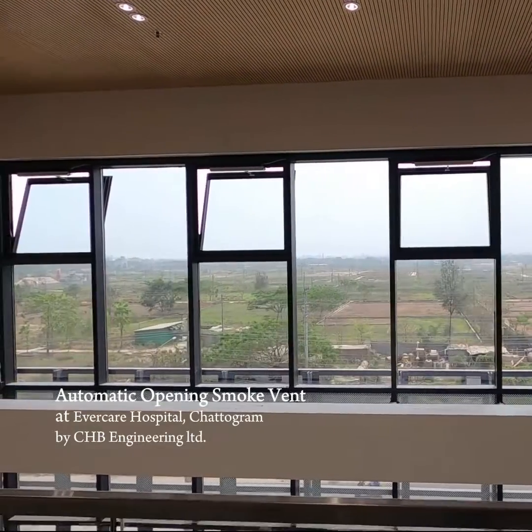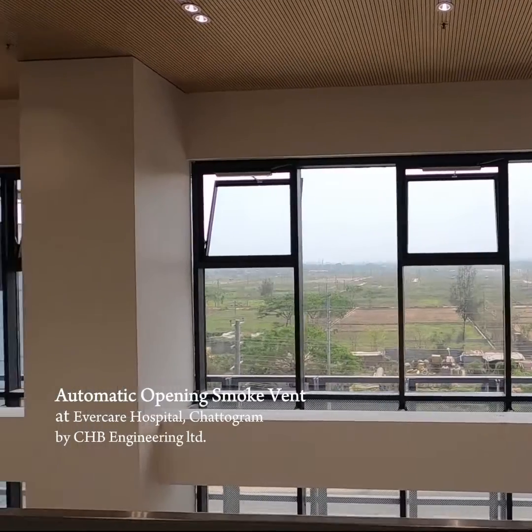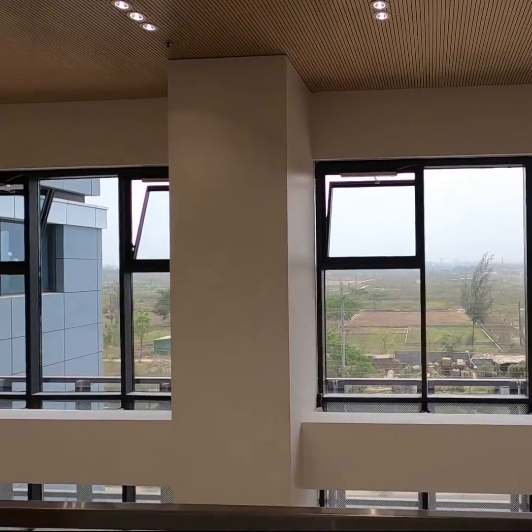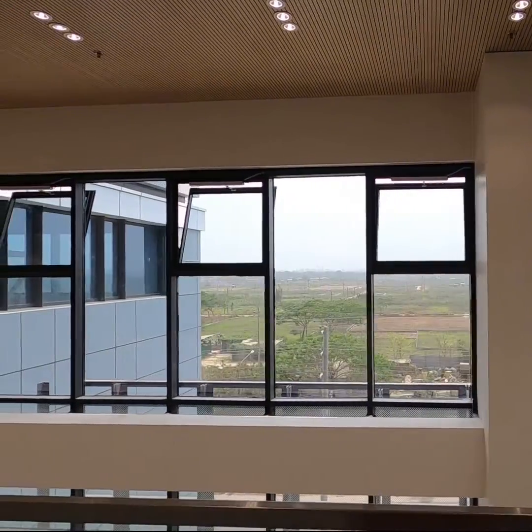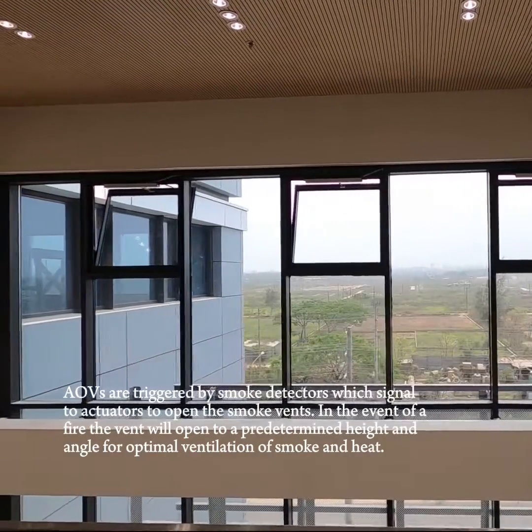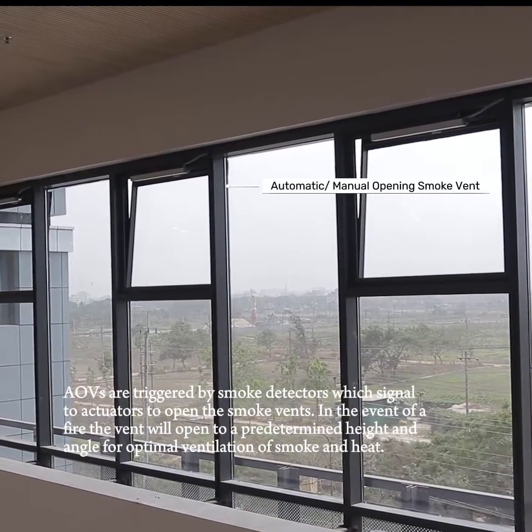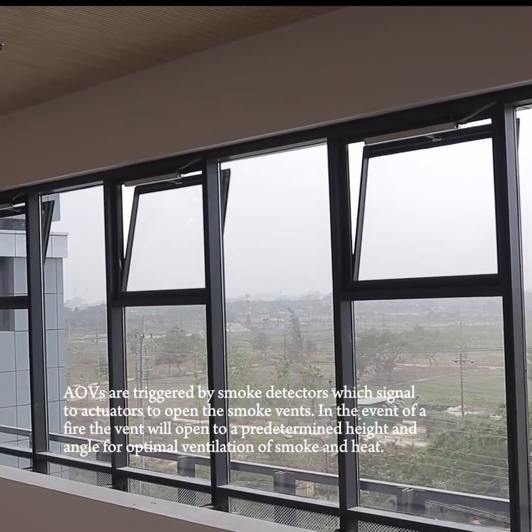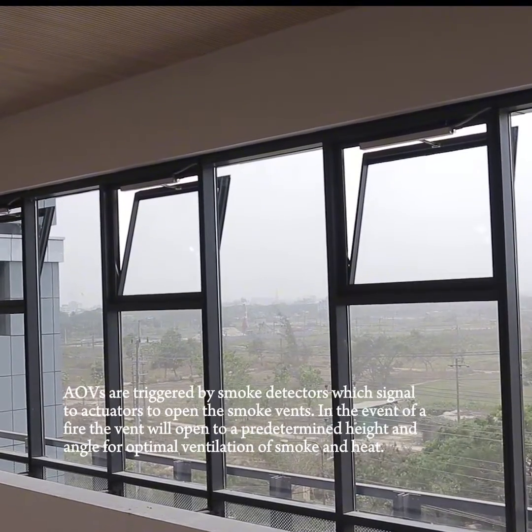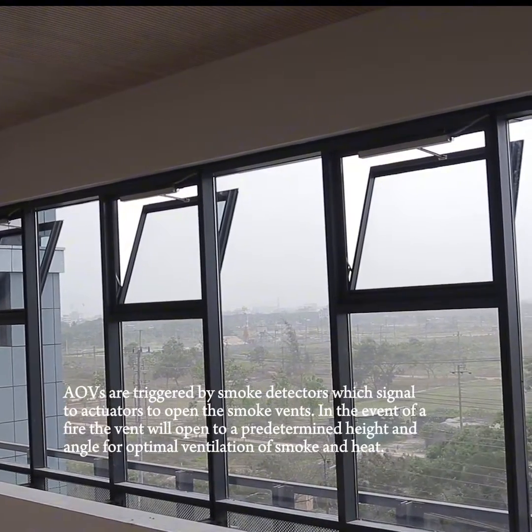Automatic Opening Smoke Vent at Evercare Hospital, Chattogram, by CHB Engineering Ltd. AOVs are triggered by smoke detectors, which signal to actuators to open the smoke vents in the event of a fire. The vent will open to a predetermined height and angle for optimal ventilation of smoke and heat.